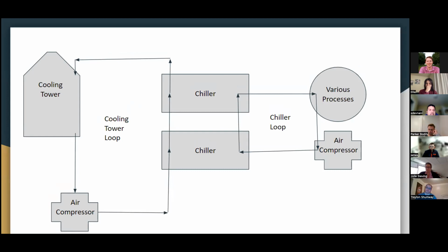So is there a reason that they didn't put both those air compressors there in the first place? Have you asked that question? Yeah. I believe the case was they added an addition to the building, which when they did, they put the new air compressor on the cooling tower, but left the previous air compressor on the chiller loop. So they may have had air-cooled condensers on the chillers first and then switched to water cool and added that whole water side later. And that might be why you have it this way. That might just be worth asking about. If that was the source, that would be a curious thing to know.